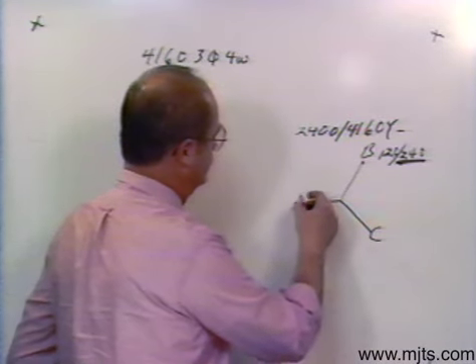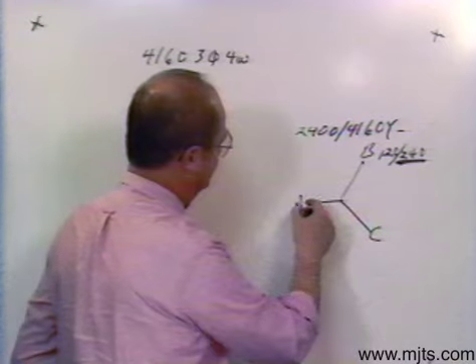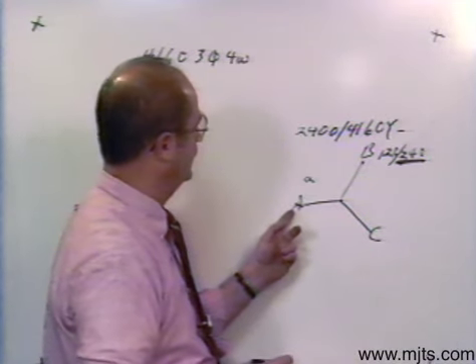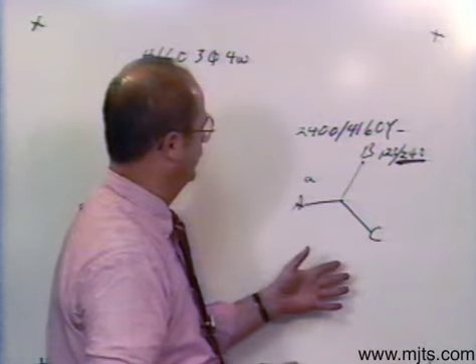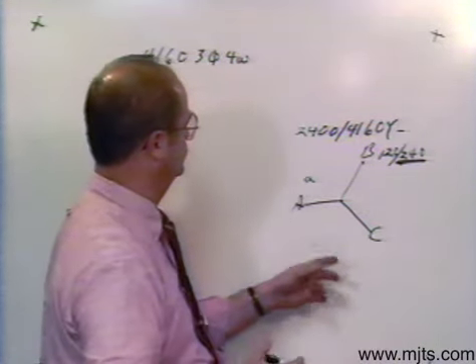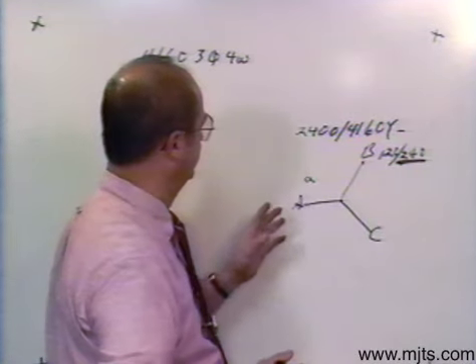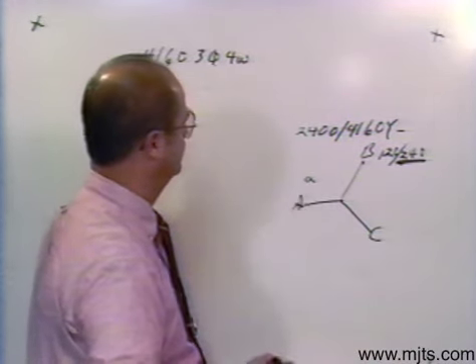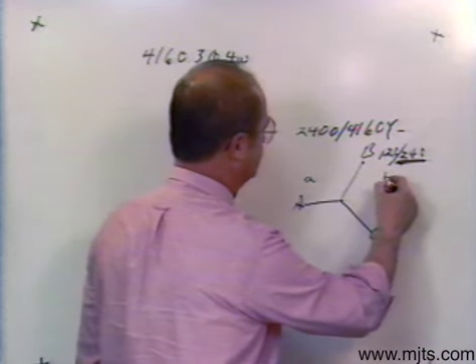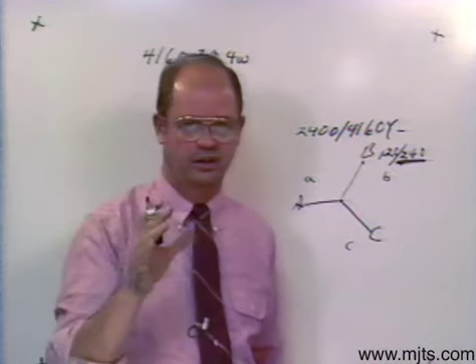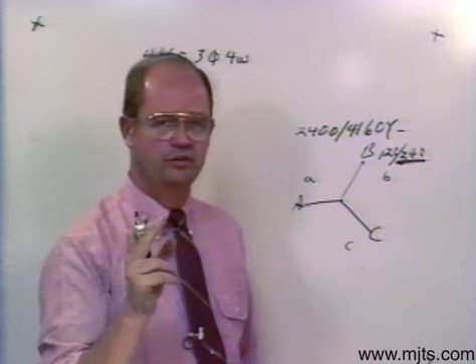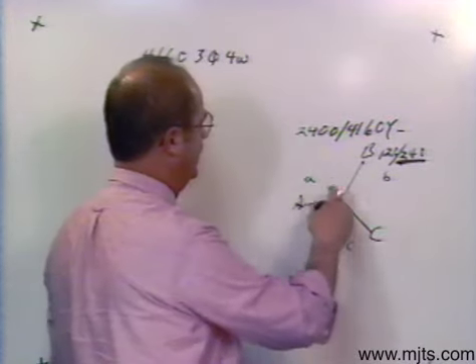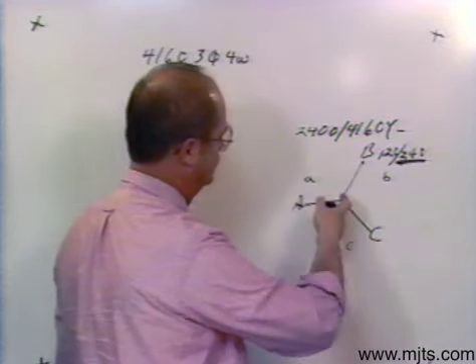If A goes 30 degrees further, then my low side is going to move up there. When you identify your phases, on the high side use upper-case letters, and on the secondary diagrams — the low side — use lower-case letters. Now I'm just going to superimpose my diagram right on top of this. If A goes 30 degrees, B goes 30 degrees, and C goes 30 degrees — that's where they're going to end up. If you've drawn it right, all your lines will be parallel with other lines. From high to low and low to high, there will always be lines that are parallel with one another.